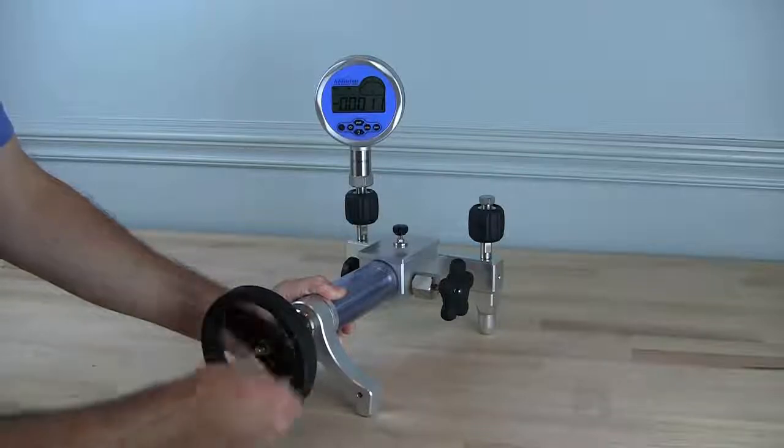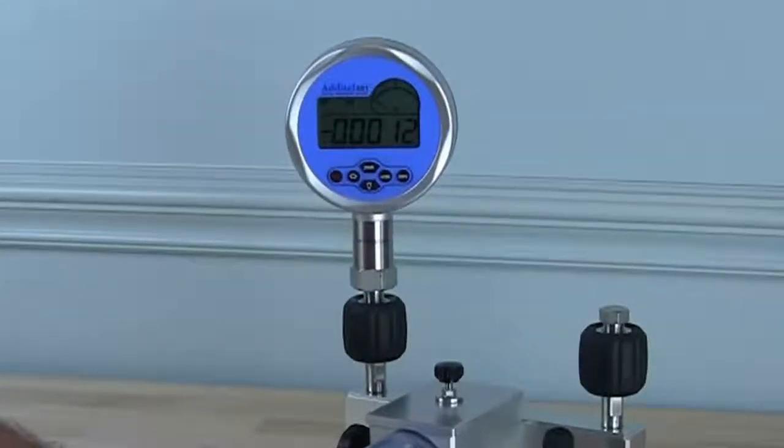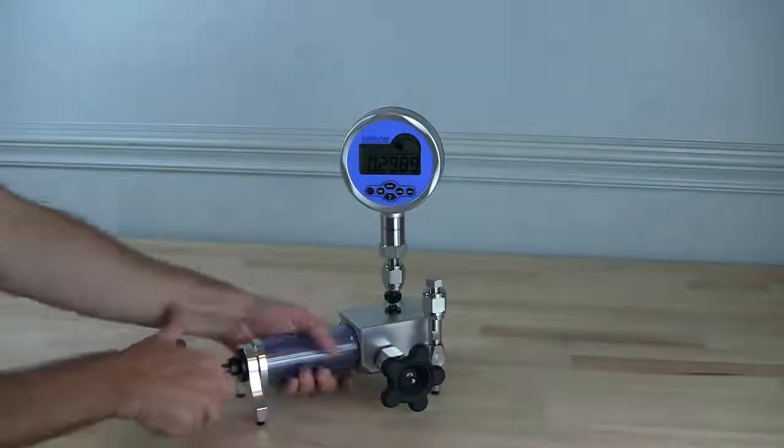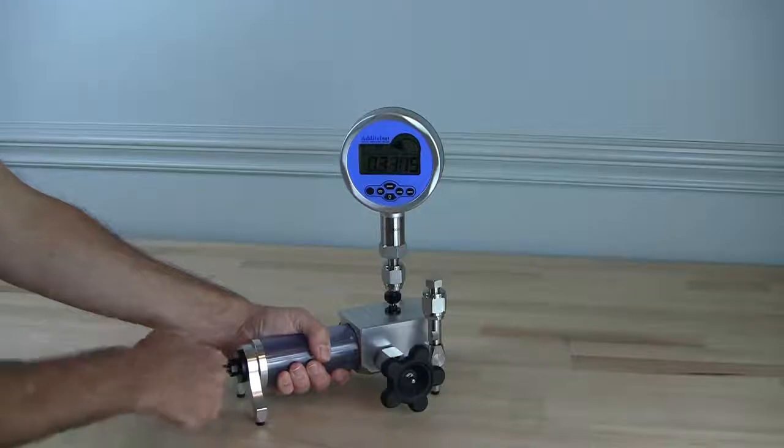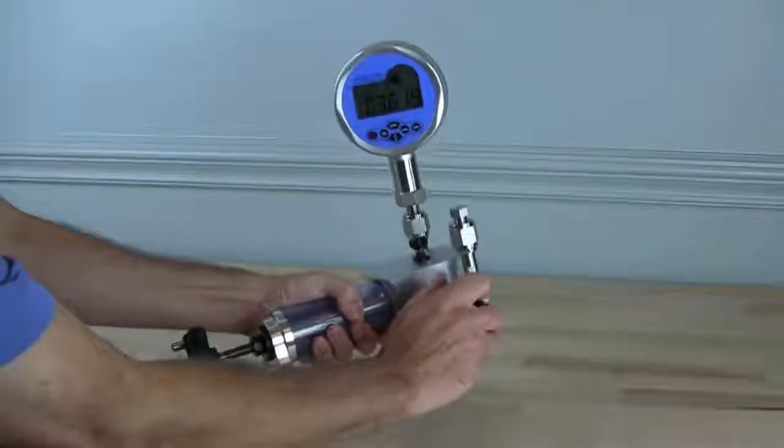Both pumps can also generate minus 12.5 PSI of vacuum by rotating the variable volume screw press counterclockwise. The ADT925 weighs in at only 3.8 pounds and is ideal for portable applications.